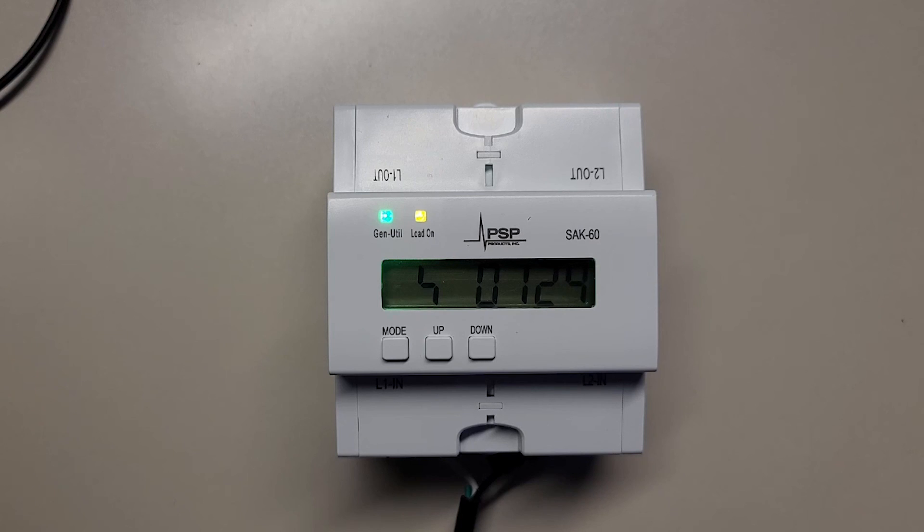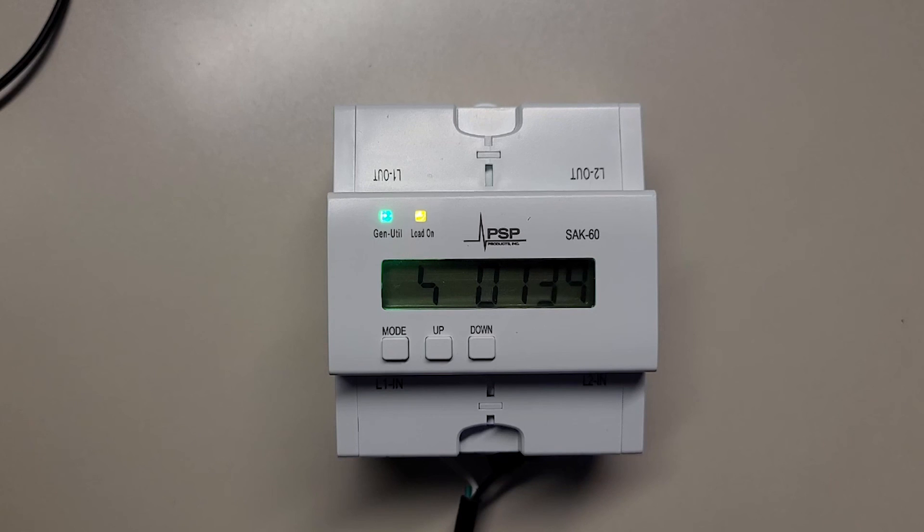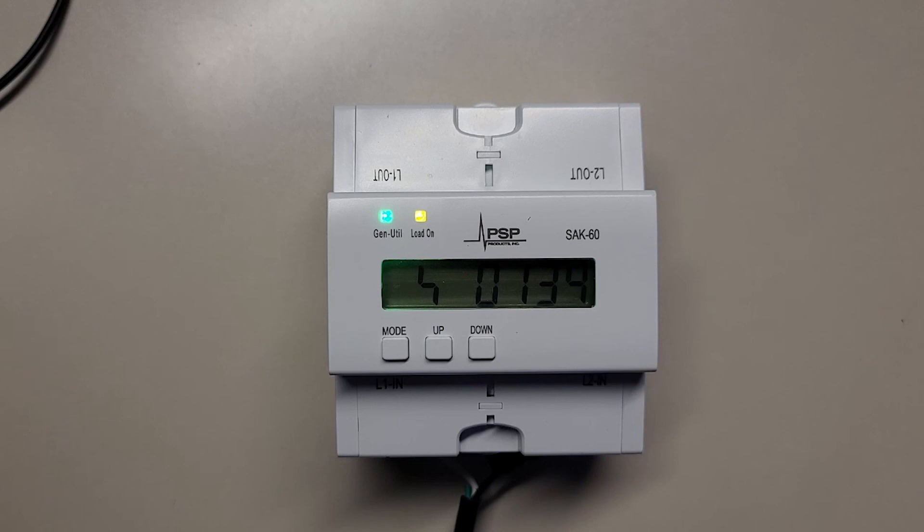When utility returns, there will be no loss of power, but after one to three minutes, the SAK will realize it is seeing a utility sine wave. There will be a short countdown timer. The relay will close, and the SAK will go back to sleep until the next power outage. It's as simple as that. You're done. You've set it up for lockout. You can go home now.